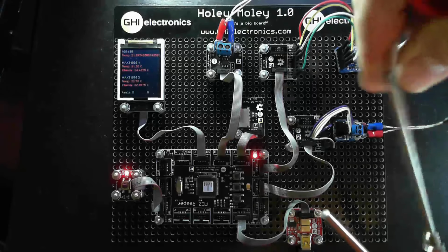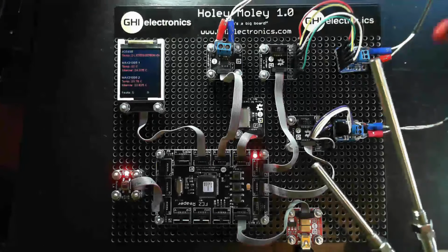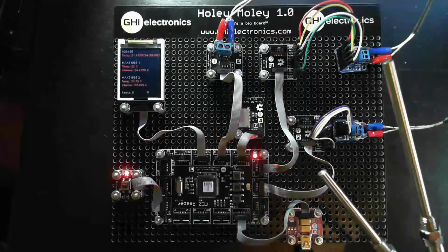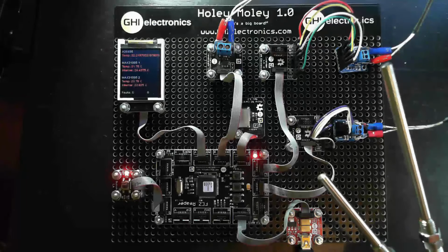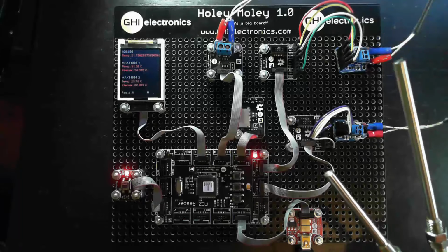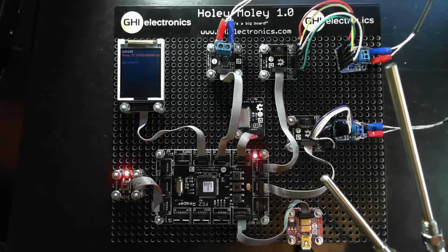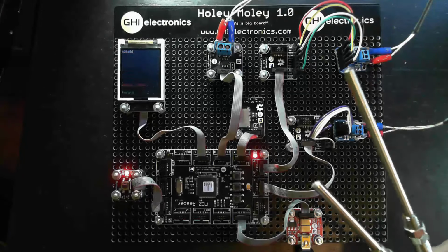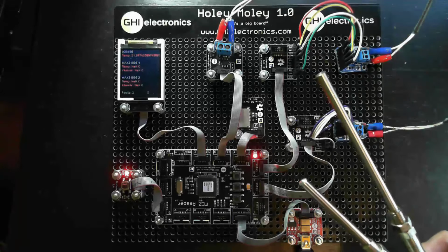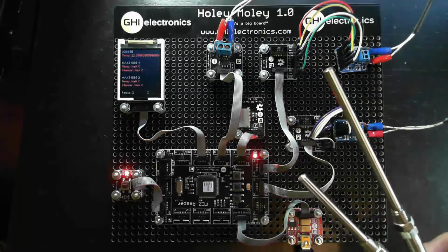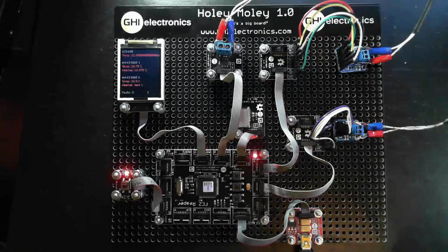If I had this wired up backwards and grabbed that probe, it would start getting colder, and then I'd know I need to reverse the connections on the breakout board because I've got it wired up wrong. That's just a quick test I always run to make sure the connections are proper.